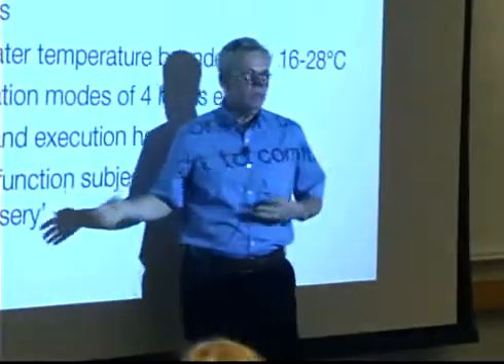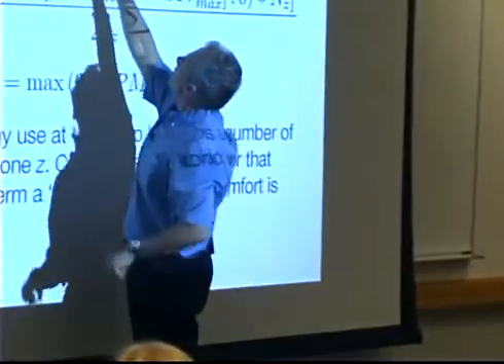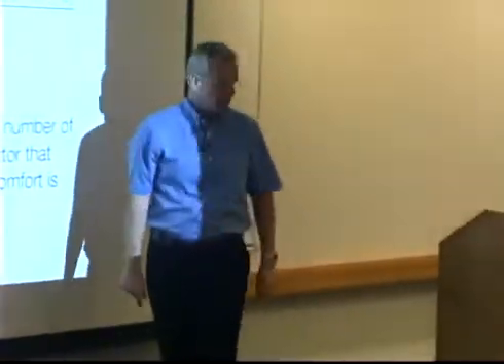Now, if we just wanted to minimize energy, then what would you do? You'd never turn the system on, right? So in order to prevent that from happening, in order to prevent people from freezing or being overheated, we had to introduce consideration of comfort, and we did that through a term called misery, right? How miserable are people in the building? And the misery term has to do with an index used in our industry called predicted mean vote. So what you get basically is energy, and you get that comfort penalty P, which is a misery term, and the sum of the two is to be minimized.